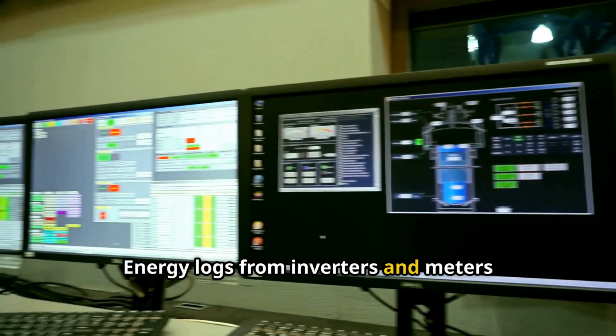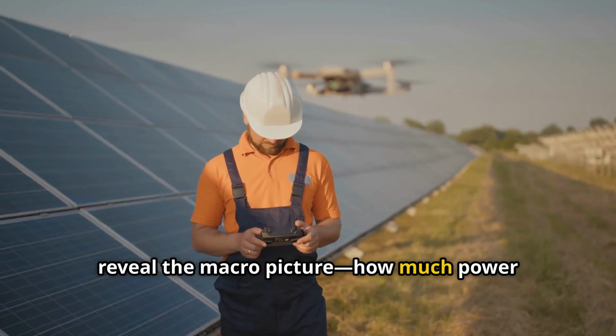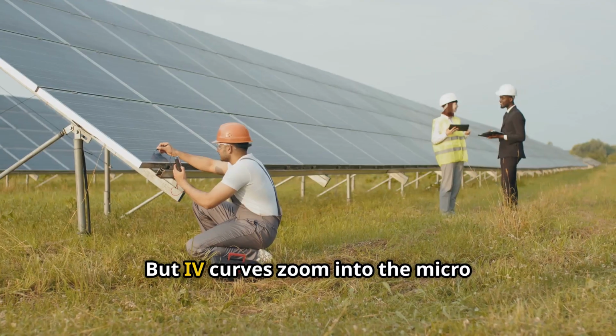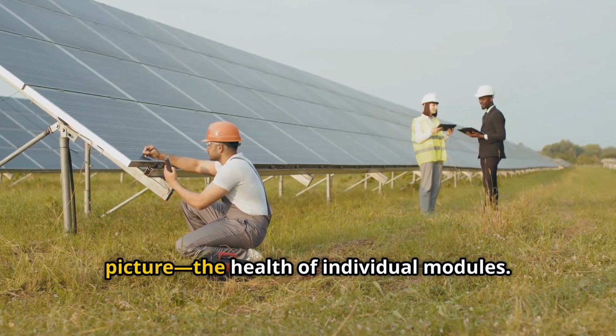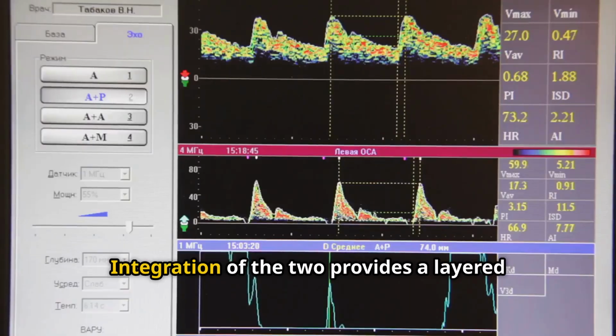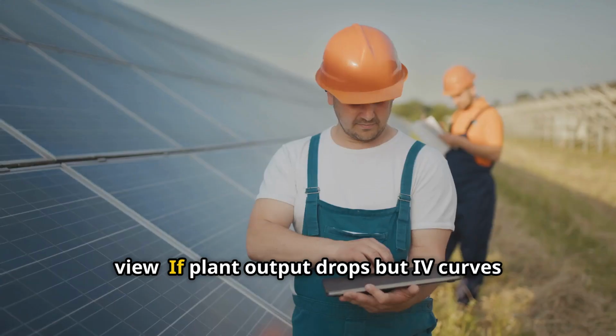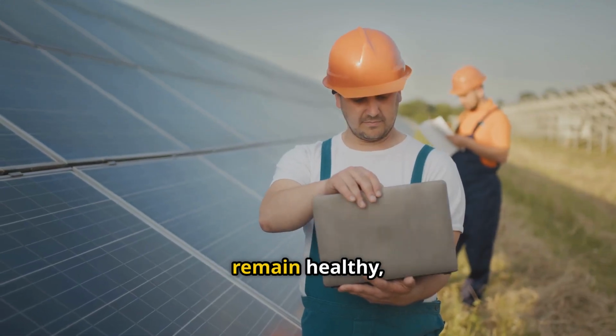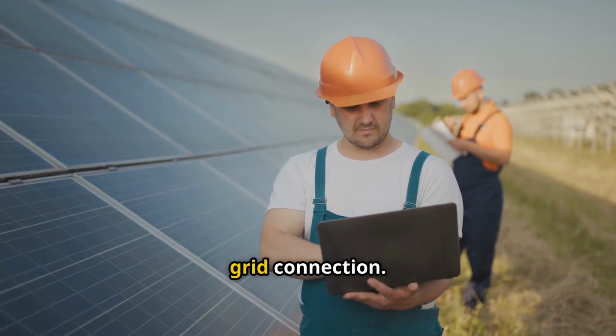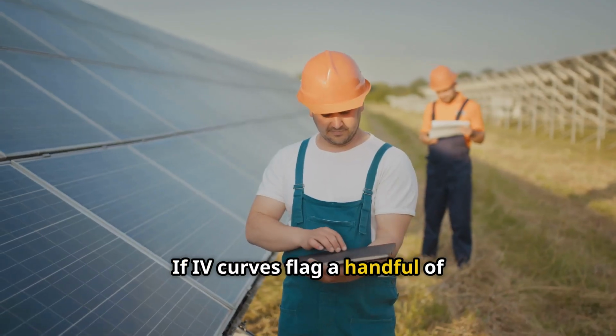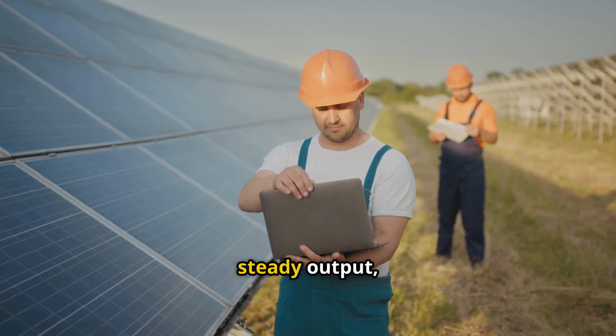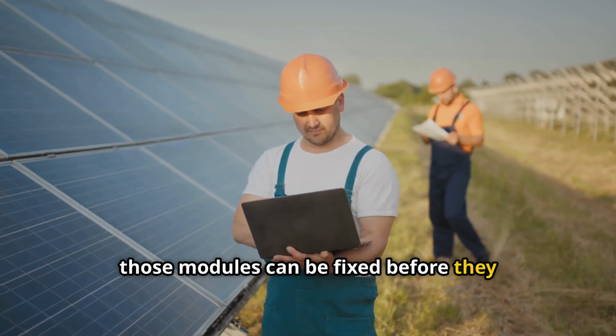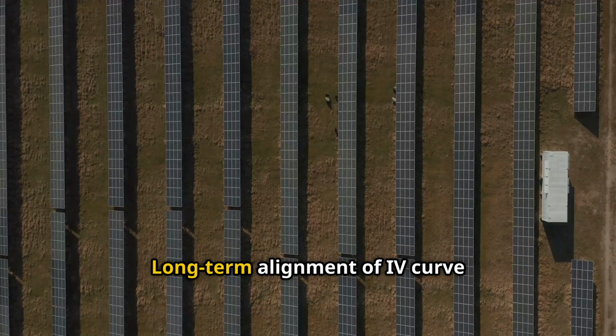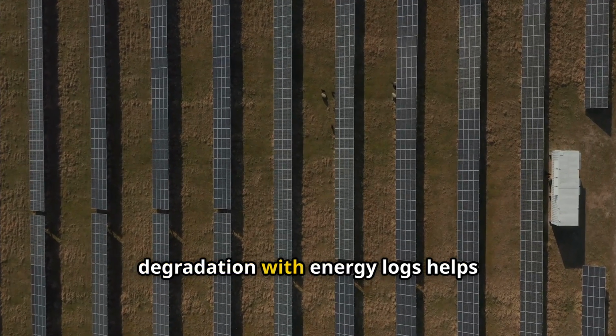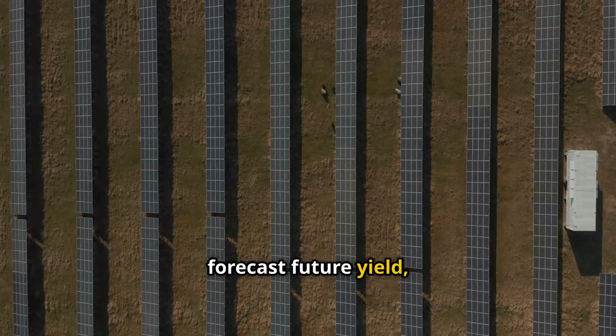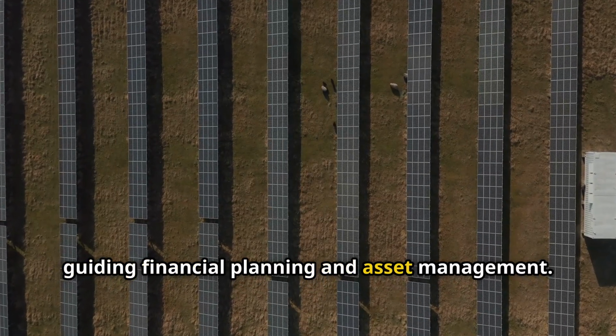Energy logs from inverters and meters reveal the macro picture, how much power the plant delivers to the grid. But IV curves zoom into the micro picture, the health of individual modules. Integration of the two provides a layered view. If plant output drops but IV curves remain healthy, the bottleneck may be at the inverter or grid connection. If IV curves flag a handful of underperforming modules while logs show steady output, those modules can be fixed before they drag down entire strings. Long-term alignment of IV curve degradation with energy logs helps forecast future yield, guiding financial planning and asset management.